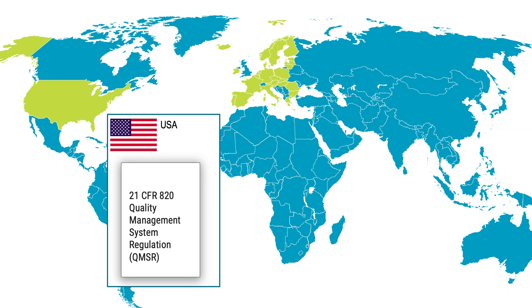There is an ongoing change regarding regulations in the US market. At the beginning of 2024, the FDA issued the Quality Management System Regulation Final Rule. The new Quality Management System Regulation, abbreviated QMSR, is set to replace the current QSR in the United States. The new rule aims to align the FDA regulations with the ISO 13485-2016 quality management for medical device standard, making it easier for medical device manufacturers to comply with regulatory requirements in different markets. The QMSR emphasizes the need to establish and implement process validation procedures to ensure that the manufacturing process consistently produces products that meet predetermined requirements. The QMSR will be part of 21 CFR Part 820, so moving forward I will refer to the US regulations as 21 CFR Part 820.